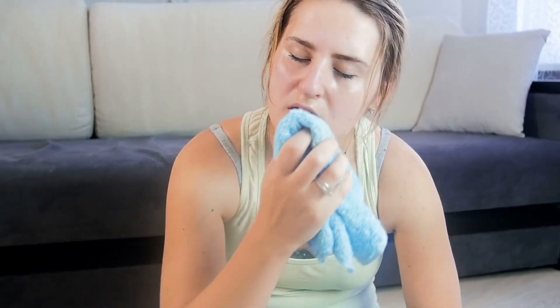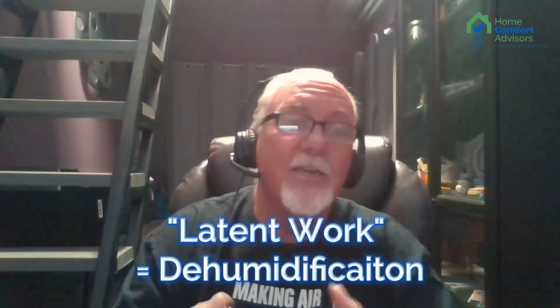It's counterintuitive. All of a sudden rooms aren't feeling as comfortable — well, you just cut airflow by a third. You're not getting enough air moving, so it feels more humid. Or it's super dry, because you've slowed the air down so much that we're doing a whole bunch of latent work that maybe we didn't need to do.